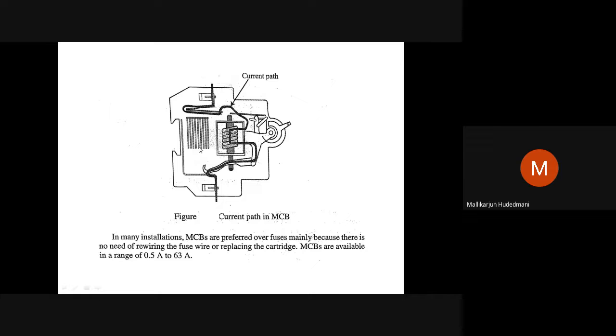In that way, this miniature circuit breaker works. So therefore, it has an incoming lead, an outgoing lead, and a solenoid coil, which allows the current to flow through it, and a lever to turn on, turn off, and reset. Something is called reset. When it is tripped down, I have to force it back. It's called reset. Then there is an arc chamber.